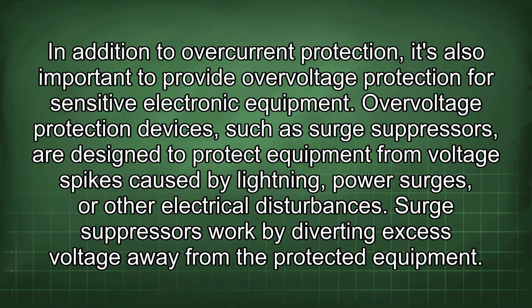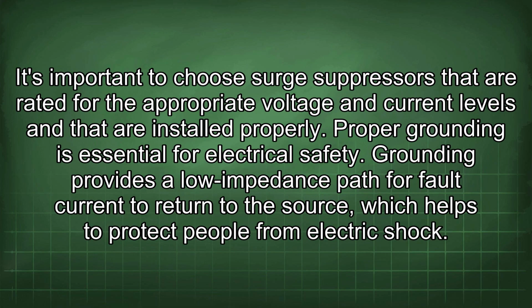In addition to overcurrent protection, it's also important to provide overvoltage protection for sensitive electronic equipment. Overvoltage protection devices, such as surge suppressors, are designed to protect equipment from voltage spikes caused by lightning, power surges, or other electrical disturbances. Surge suppressors work by diverting excess voltage away from the protected equipment. It's important to choose surge suppressors that are rated for the appropriate voltage and current levels and that are installed properly. Proper grounding is essential for electrical safety.